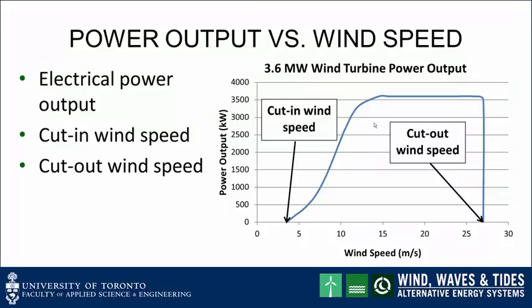What you really want to know, if you're planning a wind turbine or wind farm installation, is how the power output varies with wind speed. The graph on the right shows typical data provided by a wind turbine manufacturer — a plot of electrical power output as a function of wind speed — representative of a very large 3.6 megawatt wind turbine. Note that there is no power output until the wind reaches approximately 3.5 meters per second. This is called the cut-in wind speed; no electrical power is produced below this speed, as the turbine must first overcome internal friction before producing net output.